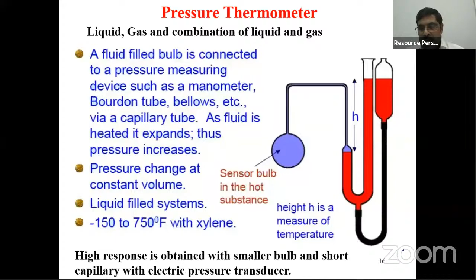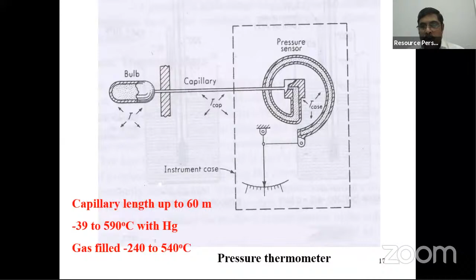Here the capillary, you can see, is directly connected to a needle through some kind of spring arrangement. As soon as you apply heat to the bulb, the gas will expand. The expansion will be given to the other capillary, which is controlled by a spring. Because of this expansion, it is transferred to the spring, where the needle is attached. So the needle will move over a calibrated scale, and then you can find the temperature. So this is about the pressure thermometer.